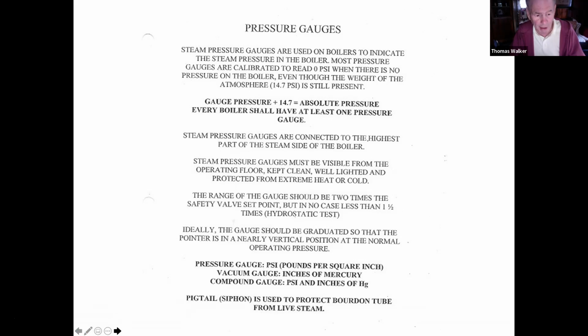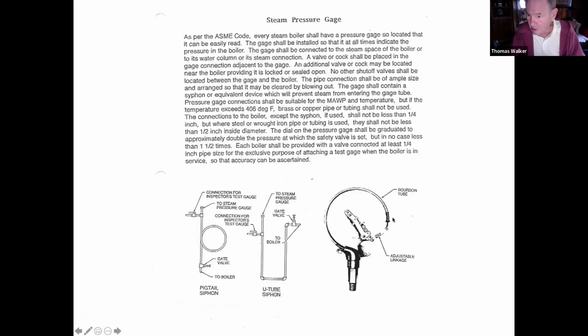And if they ask you to describe a Bourdon tube, it's simply a hollow tube that's closed at one end. As pressure is applied, the tube has a tendency to straighten out. As the pressure is removed, it returns to its original position, or shape. The end of that tube is connected by linkage to an indicator on a calibrated face. That's it. It's that simple. That's a Bourdon tube pressure gauge.